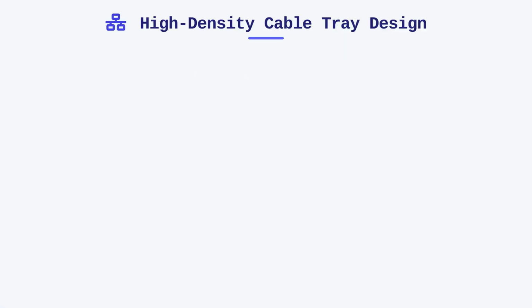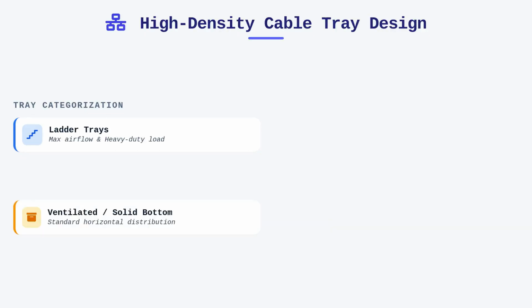When we approach the design of high-density telecommunication spaces, cable trays serve as the structural backbone for horizontal distribution. These systems are categorized primarily by construction type, including ladder trays, ventilated troughs, solid bottom designs, and wire mesh basket trays. Ladder trays are frequently chosen for heavy-duty applications where maximum airflow is required to prevent thermal buildup within large cable bundles. In contrast, wire mesh basket systems offer superior flexibility for complex routing requirements in constrained ceiling plenums or underfloor spaces.